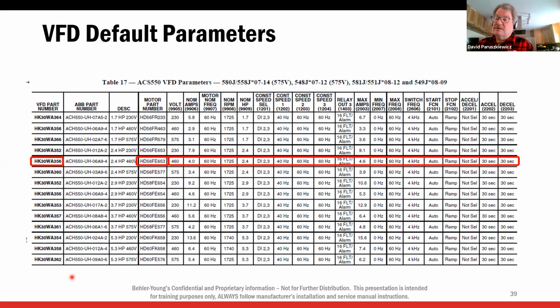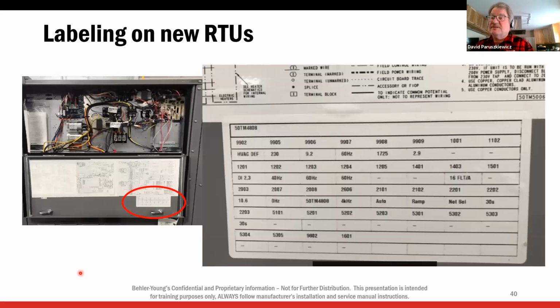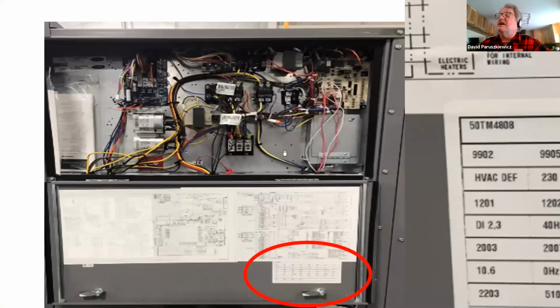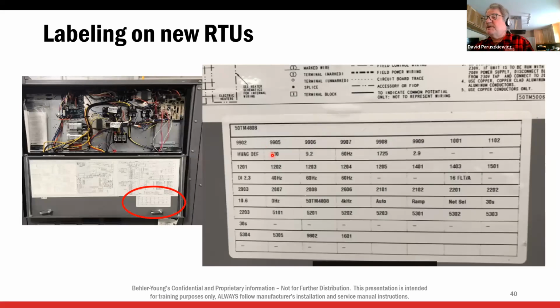Now this motor, just like the small units, gets power, and the drive gets power 24 hours a day, 7 days a week. There is no contactor in here for the blower anymore. Okay, if I look inside this control box, there's no blower contactor in there anymore. All right, that blower, motor, and VFD gets power all the time. It's always powered.